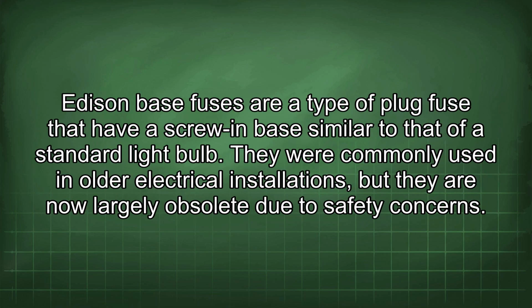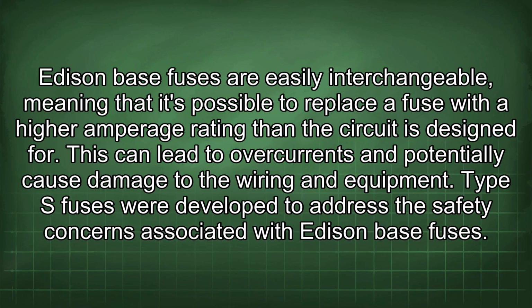Edison base fuses are a type of plug fuse that have a screw-in base similar to that of a standard light bulb. They were commonly used in older electrical installations, but they are now largely obsolete due to safety concerns. Edison base fuses are easily interchangeable, meaning that it's possible to replace a fuse with a higher amperage rating than the circuit is designed for. This can lead to overcurrents and potentially cause damage to the wiring and equipment.